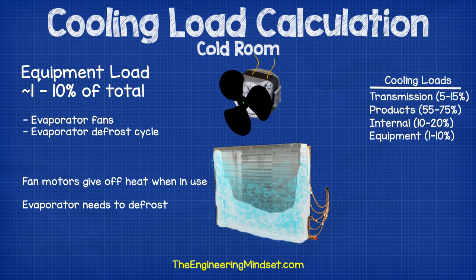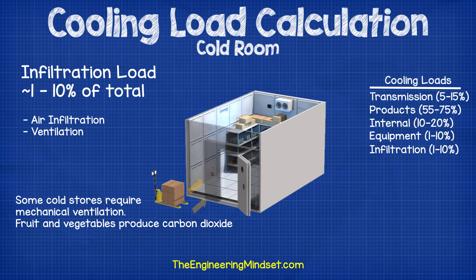We also want to account for any heat transferred into the space due to defrosting the evaporator. The last thing we need to consider is air infiltration, which again adds around 1 to 10 percent to the cooling load. This occurs when the doors open and there is a transfer of heat into the space through the air. Fruit and vegetables give off carbon dioxide so some stores will require a ventilation fan, and this air needs to be cooled down so you must account for this also if it's used.